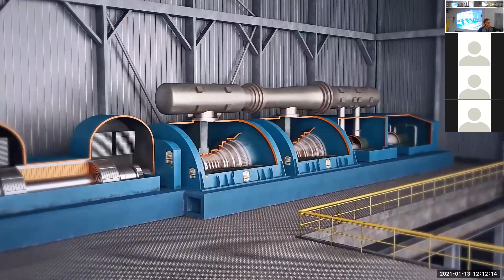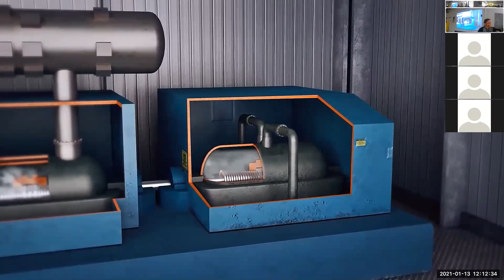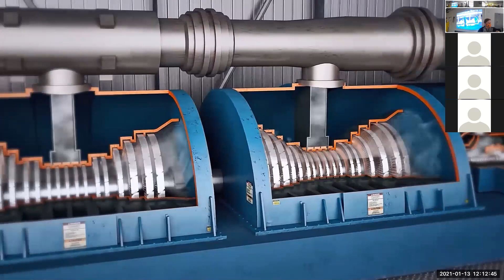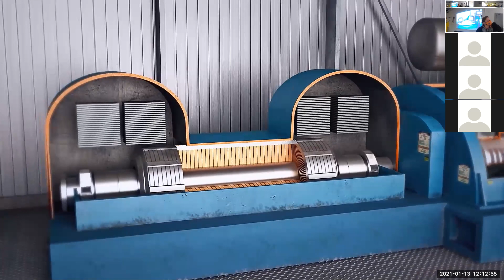Superheated steam from the boiler, which is approximately 2400 psi and 1000 degrees, travels to the high-pressure section of the turbine, where it creates the force that turns the turbine shaft. This process causes the steam to lose temperature and pressure, so it must be sent back to the boiler to be reheated to 1000 degrees. After reheating, the steam returns to the intermediate turbine and continues through the crossover into the low-pressure turbines. The force of the steam turns the turbine shaft, which turns the generator rotor at 3600 revolutions per minute. This rotation, along with the induced current on the rotor inside the generator, produces voltage, completing the process of generating electricity. The generator output is 24,000 volts, which is stepped up to as much as 500,000 volts for transmission.